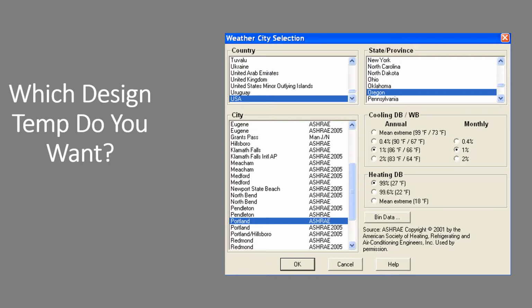The most important thing you have to do is pick the right city. So in this case, we're going to pick Portland, Oregon, and we'll take a look here at cooling. We see that the 1% cooling design temperature is 86 degrees. The 2% is only 83 degrees. If we go up here to the mean extreme, it's actually 99 degrees. The 0.4 is 90. Portland, Oregon has an unusual climate.